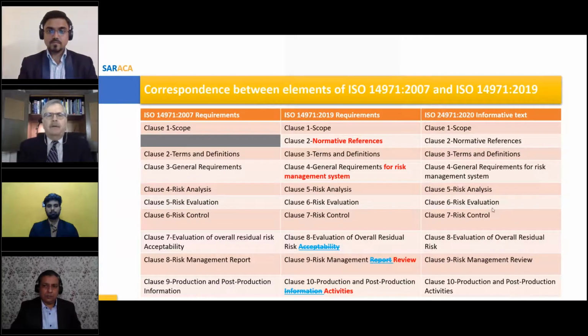The evaluation of overall residual risk has changed. The acceptability has been struck, and it just remains overall residual risk. The risk management report is now a risk management review. And again, as Arun pointed out earlier, that has to be reviewed by management prior to release of the device into the field.